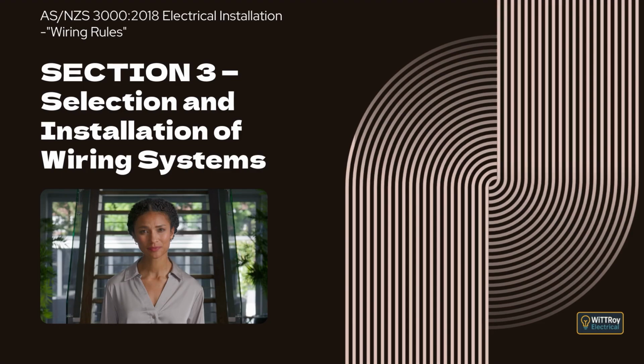Clause 3.15. Busways, including rising mains systems. This clause explains that busbar trunking systems, also called busways, must comply with ASNZS 61439.6 and must be installed exactly as the manufacturer instructs. When a busway is used as part of a wiring system, its installation must also meet the relevant installation requirements already set out in Clause 3.9. This means the same general rules for fixing, support, mechanical protection, and installation practice apply to busways as they do to other wiring systems, including the requirements that deal with penetration of fire-rated building elements.